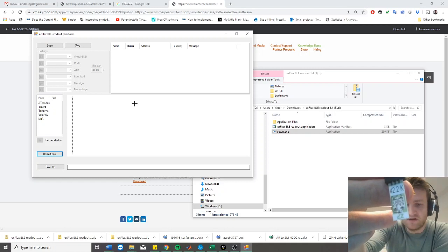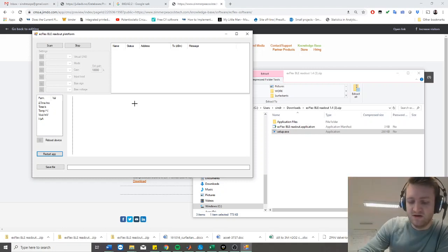And basically this looks like all our other sensors. It's a ceramic substrate. It looks like this. And on it, we populated it with some resistors and capacitors in order to act as a model for the electrochemical cell. Okay, so this one is a simple one which holds a 42.2K resistor. That's it. So we can play around with it and see if we can get some different currents.